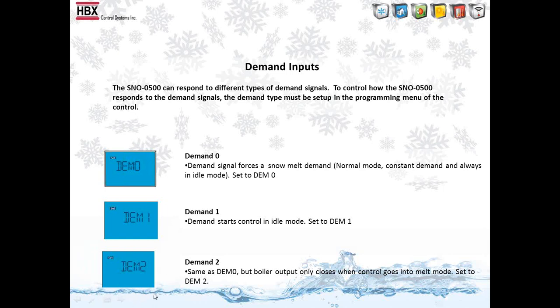So we don't care what the system temperature is. We don't care about anything but the snowfall. So once we see snow, we click the boiler output on, which would go to your BMS system, which would basically tell them to do something with the slab, that we're seeing snow. So they would control the idle temperature, they would control the melt temperature. All we would be telling them is that we've seen snow.